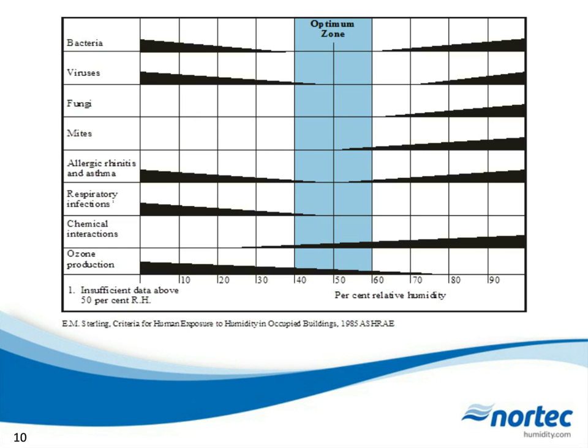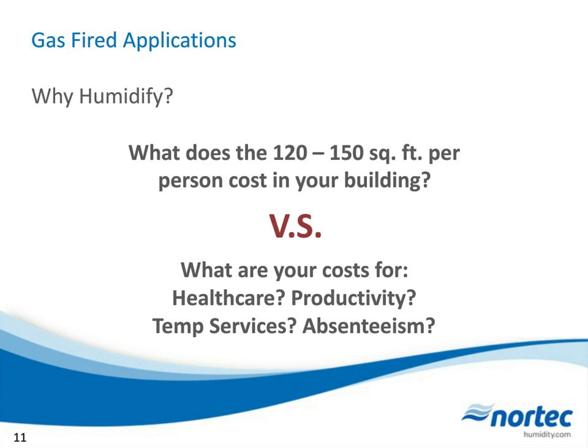The ASHRAE community is actually working on an updated version of this chart, but what we see is that bacteria and viruses, as well as allergy-causing fungus, tend to die off much faster within the optimum zone highlighted on screen. Anywhere between 40% to 60% relative humidity is where we like to hold our spaces in order to kill flu viruses or dangerous bacteria that could make us sick. There's a cost associated with humidification, but you have to compare that cost against healthcare costs, productivity costs, temp service costs, and absenteeism.